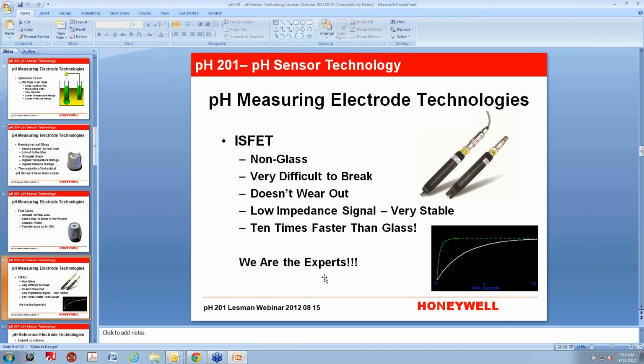It doesn't wear out. A FET doesn't have a set of active sites that are being used up by hydrogen ions. It's actually creating a field, and it counts hydrogen ions coming through a gate in that field. So it's not going to wear out. It can be damaged by some process fluids, but when you get in the middle range, I would say that you're probably in pretty good shape of not having it damaged. It has a very low impedance signal. It doesn't have the high impedance that a glass pH sensor has, so it's going to be more stable in terms of electrical noise getting on it. You've probably had times when you've seen your pH sensor get whacked out, and maybe it's due to some high voltage valve or pump or something nearby.